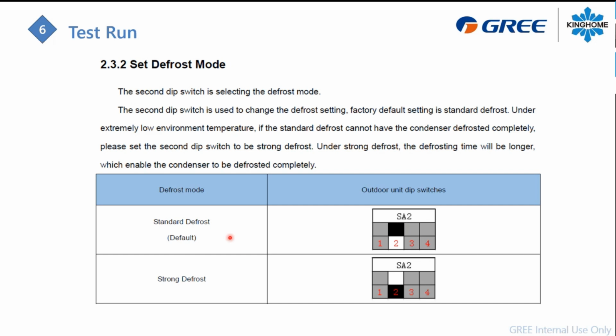If in a certain case you have ice built up in the unit and you have difficulty removing the ice or snow, you can make it a strong defrost. Just put the power off, wait 15 minutes, then move your dip switch selection to off. That will make the system go into a strong defrost. It will defrost more rapidly, so you have more chance to remove that ice and snow stuck in the condenser coil.